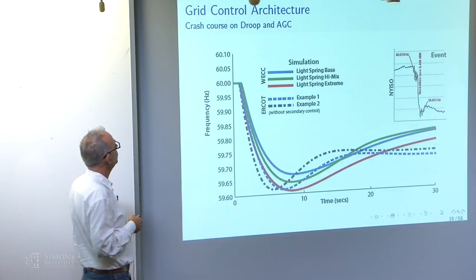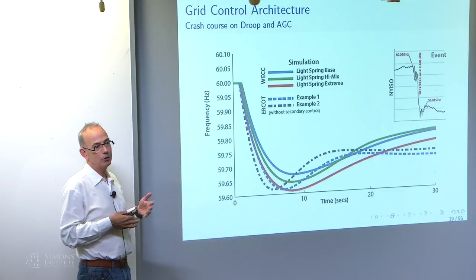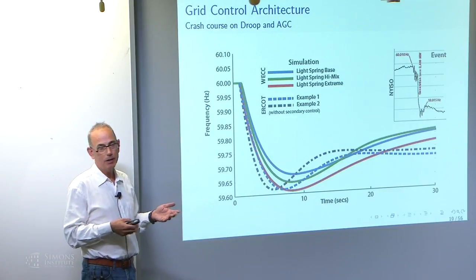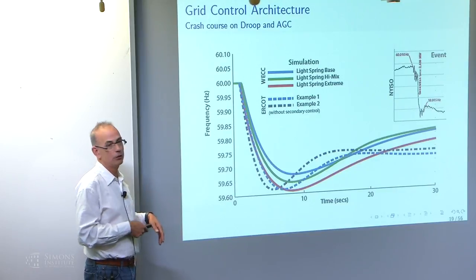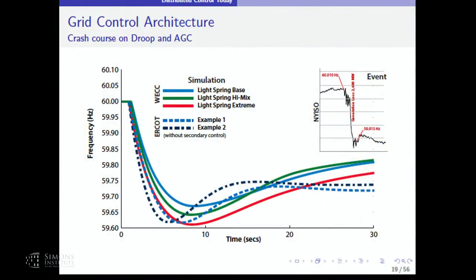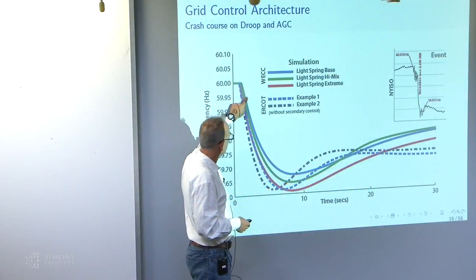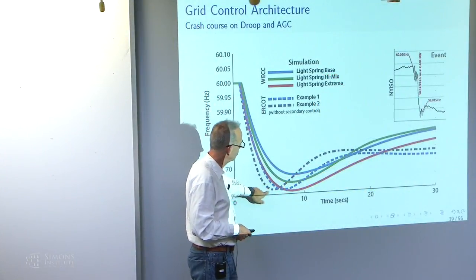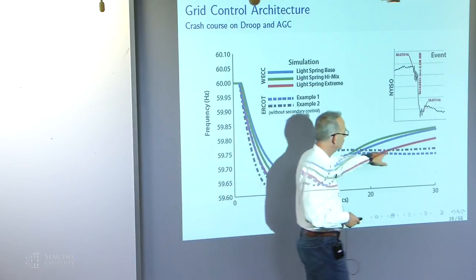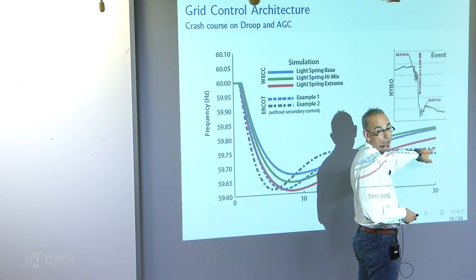If you look at the kind of model you get, you can validate it based on an event. These are simulated events where you lose 2 gigawatts of generation, or gain 2 gigawatts of load. This is like Richard Murray's step response, but upside-down because you lost something. In Texas, for a reasonable model, the frequency goes down, comes up, and goes to a steady-state value.